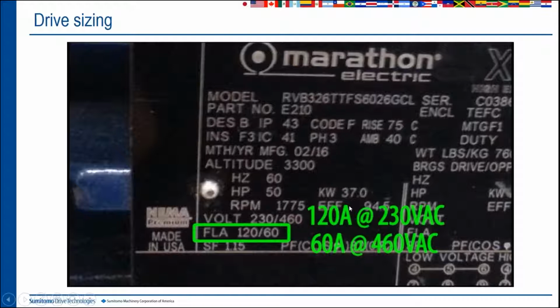It's not very clear, but for example, here behind the 120 amps, there is the efficiency, 94.5%. And the power factor is also known as cos phi. Sorry, I don't know how to say it in English. But when you see cos phi, this is the power factor.